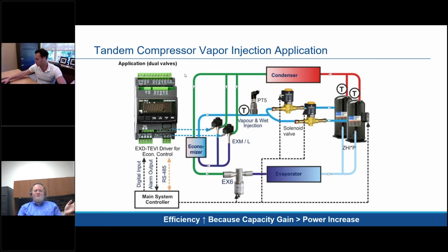It can be an OEM compressor controller, or it can be the system controller. It can have that logic in there as well. But what this is doing is it's monitoring the temperature of the scrolls itself, and it's determining, okay, this is how much vapor we need to bring back to those compressors by controlling the superheat to keep that discharge temperature cool. And then also, whenever it moves the wet injection, it does the same thing. It controls how much wet injection is brought back to the compressor, which is a mixture of vapor and liquid, which needs a lower superheat value than what that 7 to 10 degrees typically would with just vapor injection itself. This is going to communicate with the main controller in the system as well.